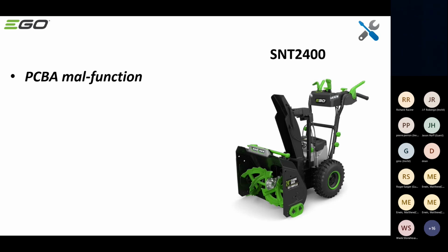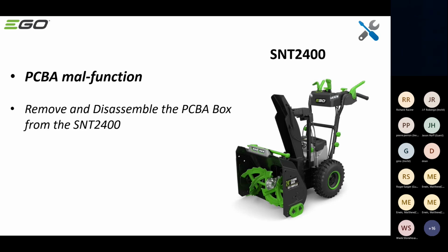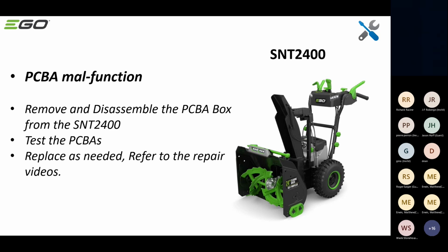In that case there's a PCB malfunction, and you'd have to remove and disassemble the PCBA box. It's a repair where you take a few parts out, and once you get to the box, you test the PCBAs like we did on the single stage unit. It's not as easy to access the PCBAs, but it's not that difficult either—just more time consuming than the single stage. Once you test the PCBAs, if any are bad, you just replace them.